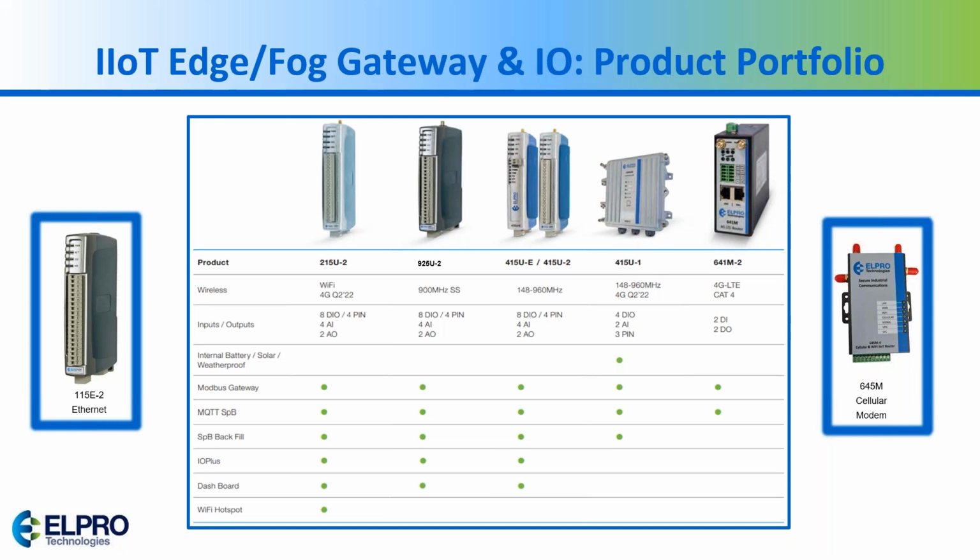So what I've done is looked up hardwired units that are DIN rail mounted that are in an enclosure, and some of them, like the Weidmüller one, and actually the Opto 22 one, is Class 1 Div 2. So you can add that Mosquitto broker onto those units because it runs Linux.